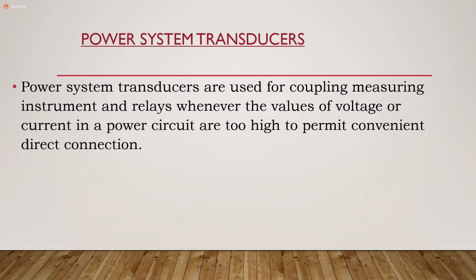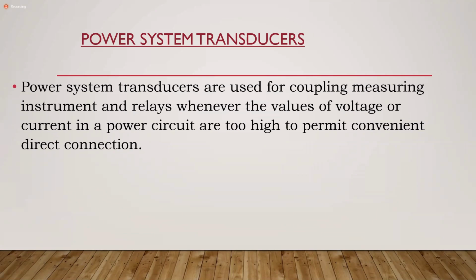Now, key here is that once you introduce these transducers, you have to ensure that the information you're getting on the output is a true reflection of what is on the system. And when we delve deeper into transducers, we realize there are certain standards applied to them in terms of the level of error that will be involved. Every time I go into this, I touch base on what you have done in your magnetics, because we delve back into some of that. But let me not stray from the main point. The key is that you have to be able to represent or reflect exactly what is on the system.